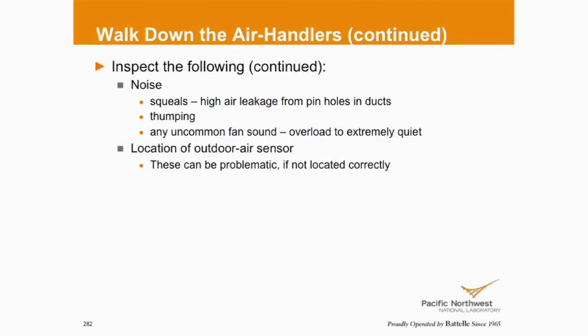So we talked about noises, location of outdoor air sensor. I would say 95% of the time we run into this. And again, we're using outdoor air sensors for calculating enthalpy. We're using outdoor air sensors for determining resets on discharge temperatures. We're doing it for a lot of things. Real important to validate where that sensor is located.